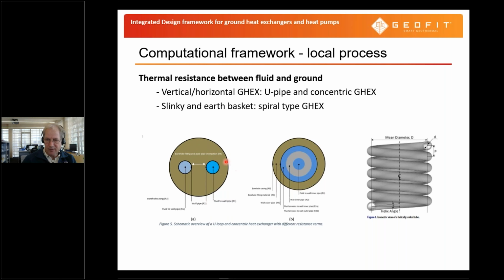And you can imagine that there are a lot of different processes going on here. But at the end, we can say there is a temperature difference between the fluid in the pipes and the wall of the borehole, which depends on the whole structure of this system. The same for a concentric borehole, where we have a small dimension pipe in a larger dimension pipe, a different set of equations, but again we have a temperature difference between the fluid in the heat exchanger and the ground.